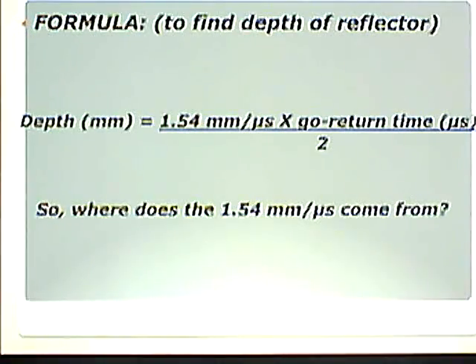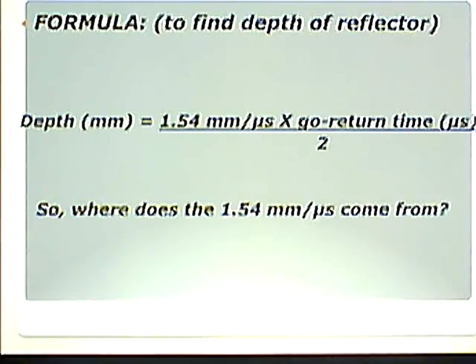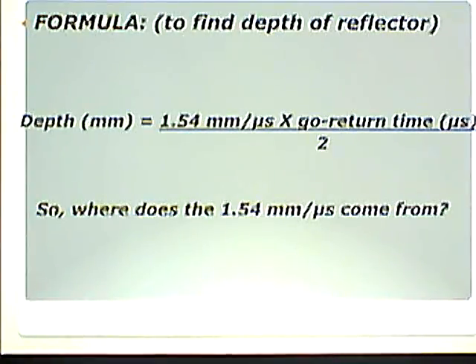The formula to find the depth of a reflector — depth in millimeters — is 1.54 millimeters per microsecond times the go-return time in microseconds, divided by 2. That 1.54 mm/μs is the speed of sound in soft tissue. It makes sense to take 1.54, multiply it by the go-return time, and divide by half, because we only want to know halfway — the one-way distance to the reflector, not there and back. That defines depth.